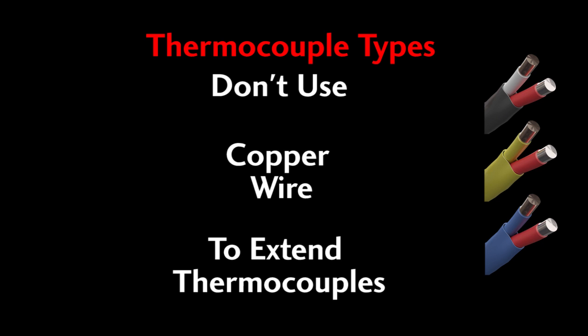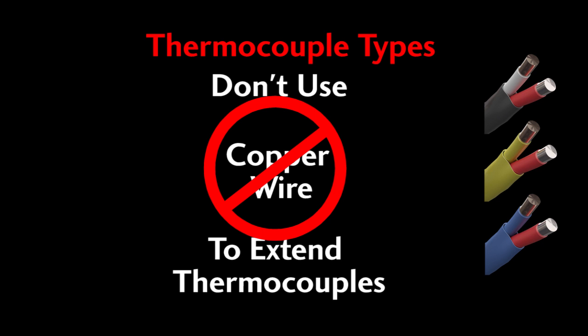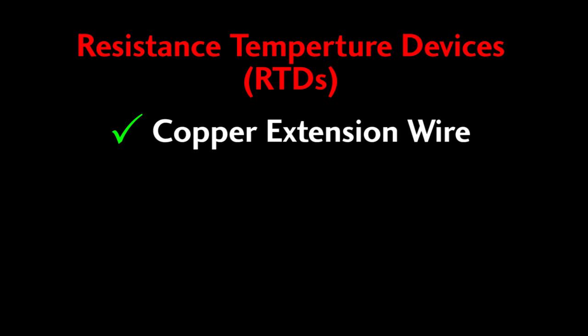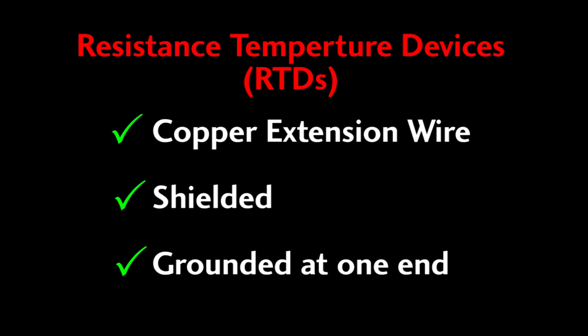Don't use regular copper wire to extend thermocouples, it will mess up the readings. Copper wire is fine for RTDs, but you will want to make sure it is shielded and that the shield is grounded at one end to reduce the noise.